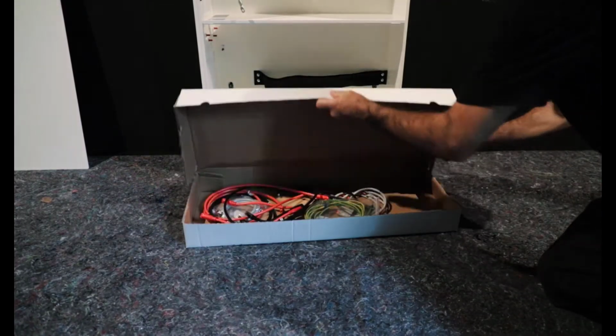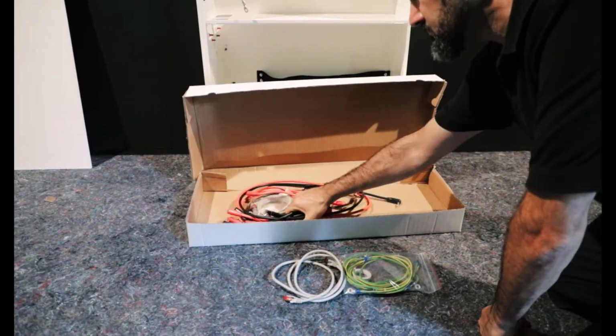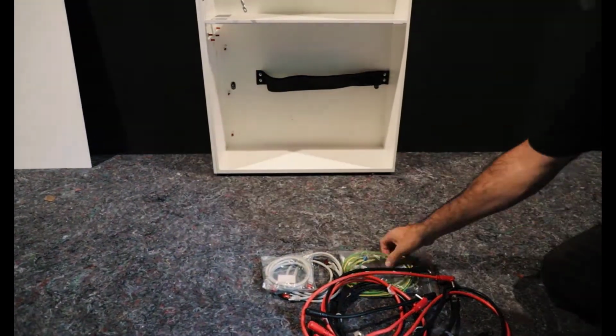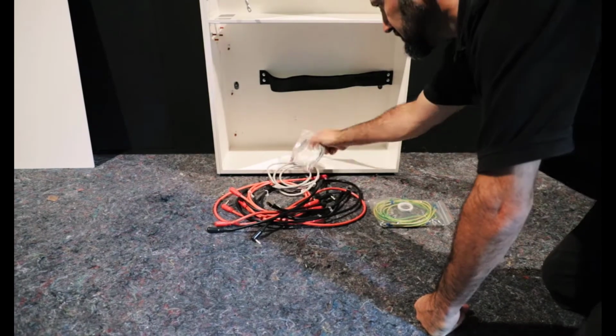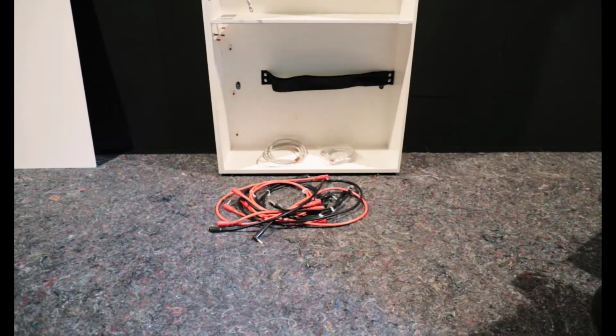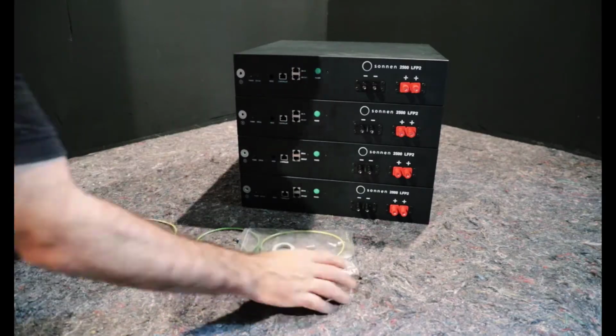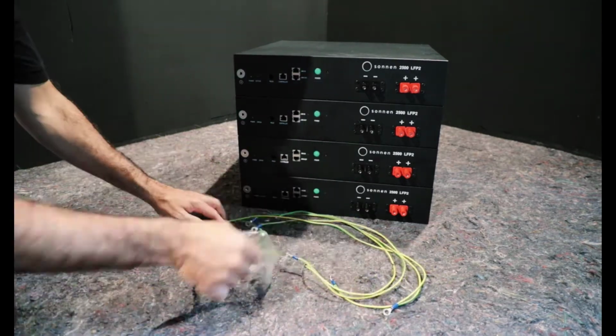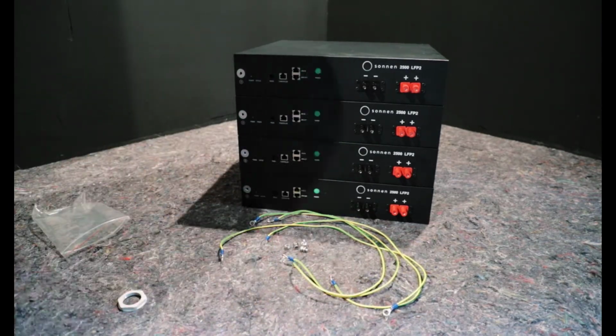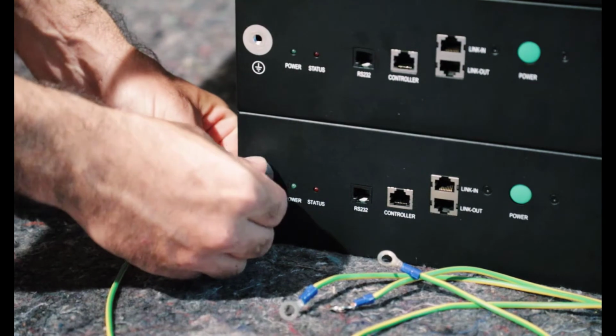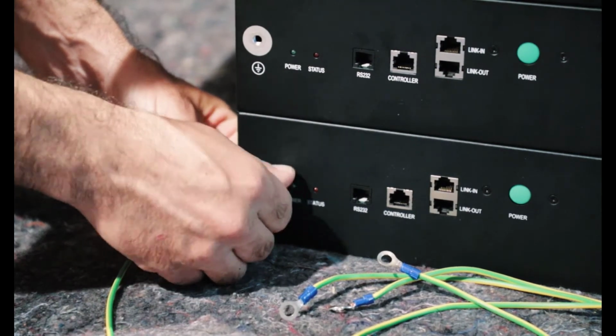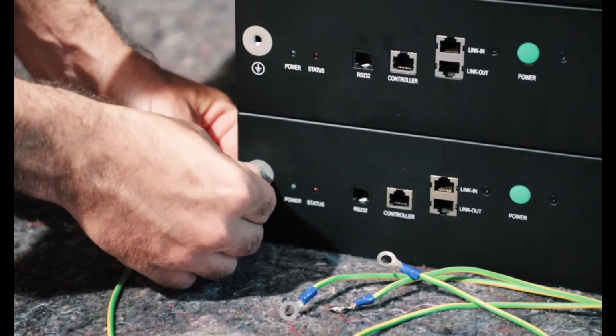So what's important then with the extension housing is to take out all the components within the accessory kit, and most importantly for now the earthing straps, because each one of the battery modules needs equipotential earth bonding, so we get those straps onto them. It can be done once the batteries are installed, but personally I think this is a far simpler procedure if you get these earth cables on prior to installing the batteries themselves.